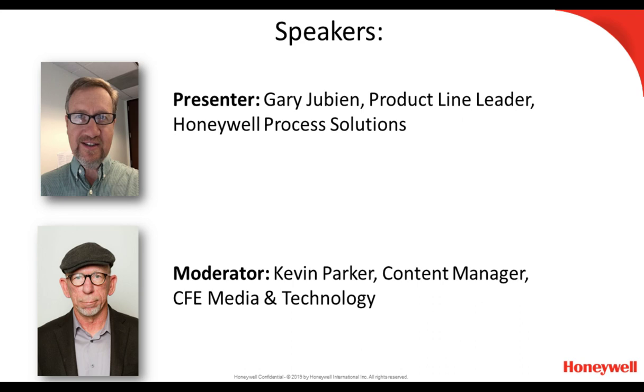Most APC applications in a lot of continuous process industries run at maybe a 30-second or 1-minute frequency. So to ask an operations person to monitor the process so closely that they can make perfect control adjustments on a minute-by-minute frequency on a unit-wide basis is an unreasonable ask, right? So typically what happens is the operators make very good moves. They'll just move the key variables at a slower frequency, maybe once or a couple times per shift, as needed. So all we're doing is similar to what the operator would do, but on a more frequent basis.